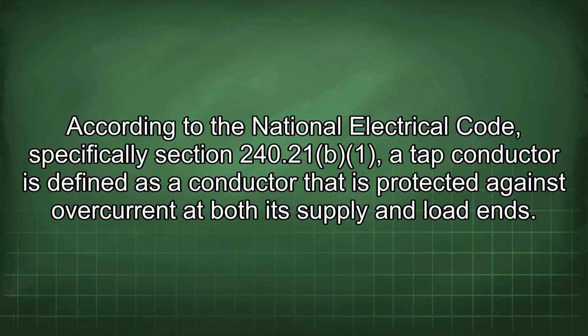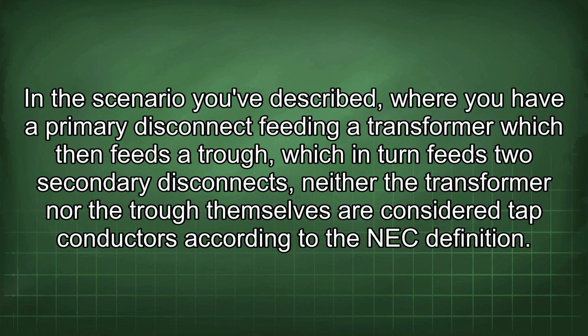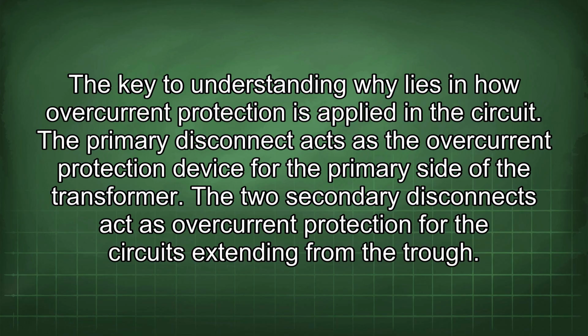According to the National Electrical Code, specifically Section 240.21, a tap conductor is defined as a conductor that is protected against overcurrent at both its supply and load ends. In the scenario you've described, where you have a primary disconnect feeding a transformer which then feeds a trough, which in turn feeds two secondary disconnects, neither the transformer nor the trough themselves are considered tap conductors according to the NEC definition. The key to understanding why lies in how overcurrent protection is applied in the circuit.